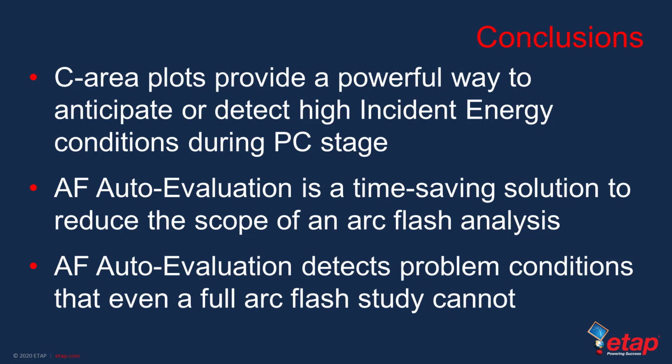In fact, by evaluating a C area plot, we have performed at least 3 or 4 independent scenarios which would be required during an arc flash study. Maximum, minimum, average, normal conditions, they're all covered with a single arc flash evaluation using this tool.